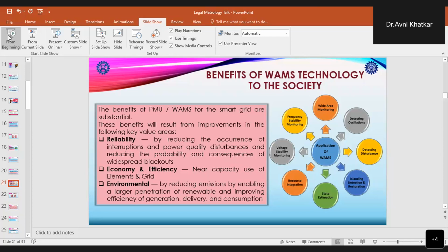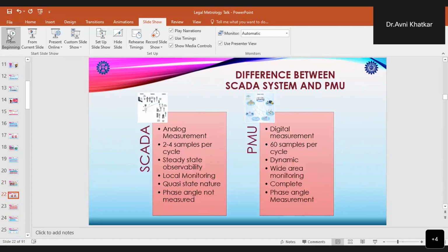And this system should ensure isolation of specific areas in case of any contingency, so as to protect the grid and prevent larger outages. Now, after talking about the benefits, as we know, till now we are focusing on SCADA systems, and now we are moving towards having phasor measurement units in the system. So the SCADA systems which were used till now are built upon 104 RTUs, and they are used in the present grid. So this present grid is primarily managed by using technologies like SCADA, that is supervisory control and data acquisition. And this SCADA system has a refresh rate of 2 to 4 samples per cycle, and hence it provides only a quasi-static grid visibility.